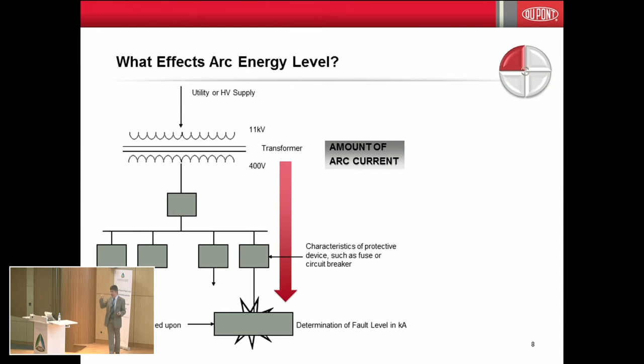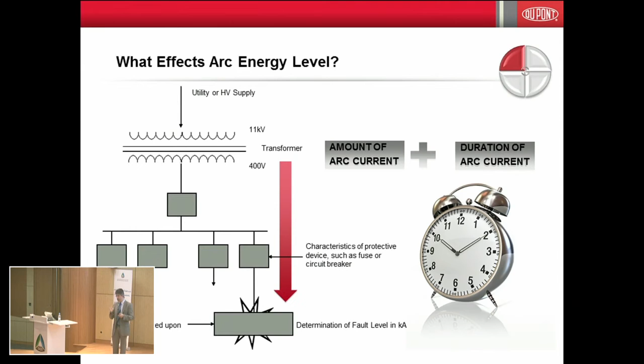What's important to understand is that the level of energy that can be emitted depends on two key parameters: the amount of current, and the duration of the current. Those two elements determine the amount of energy emitted, how much current is going through the system during the arc flash event, and for how long.